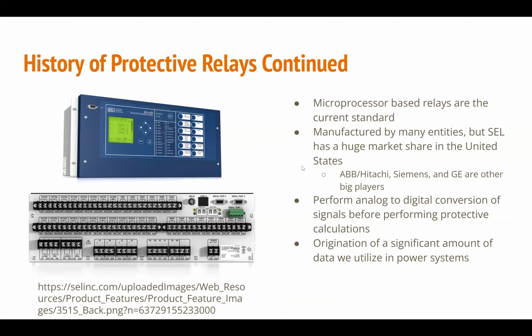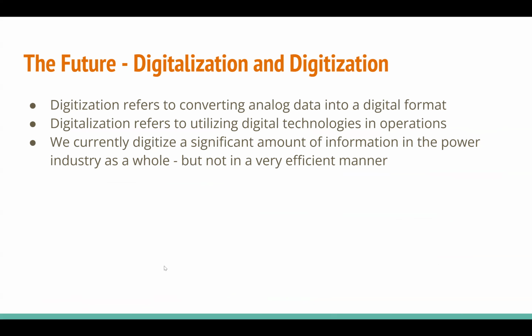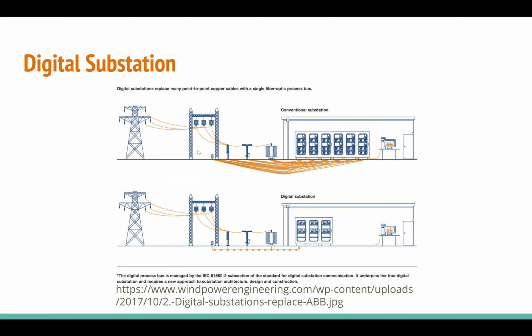So why that might be important is we would be tying secondary values onto these connections right here. If we tried to do this with primary values, then this relay box would have to be way bigger just to compensate for the safety challenges that would go along with that. When I talk about primary and secondary, primary is up in the kilovolts, and our secondary is in the tens to hundreds of volts. Our currents are in the amps versus hundreds of amps, so we're talking about values that are significantly stepped down, but proportional. Our secondary values are what get tied into these, and our primary values are what is out here at this point, actually being utilized on the power grid.